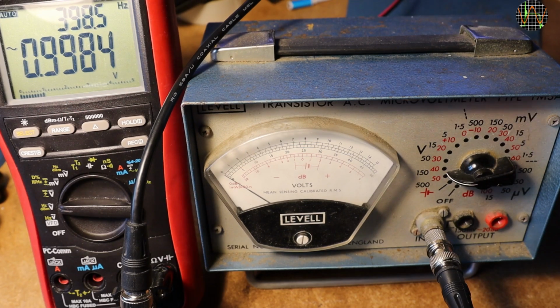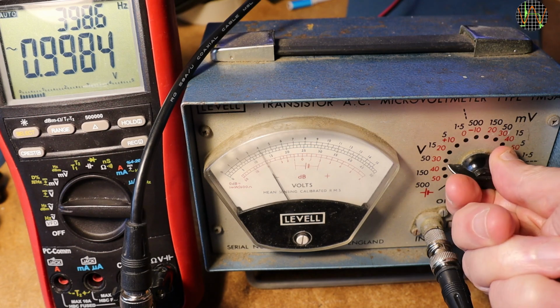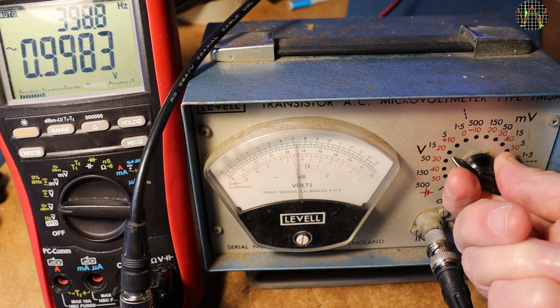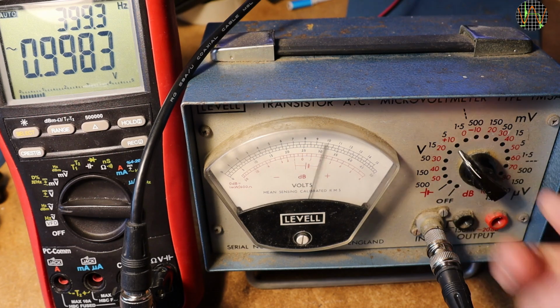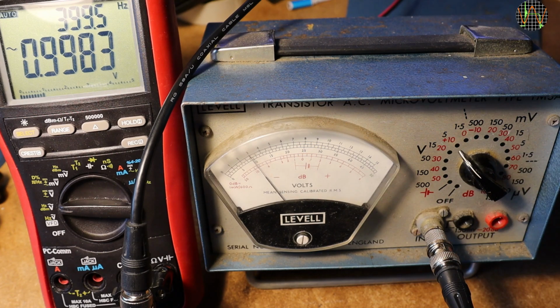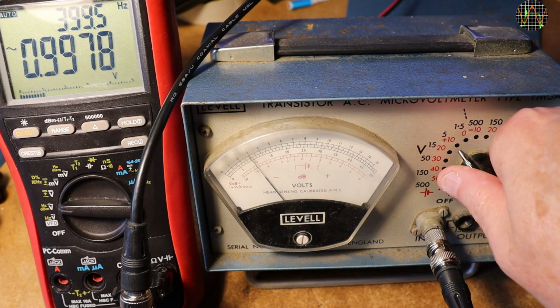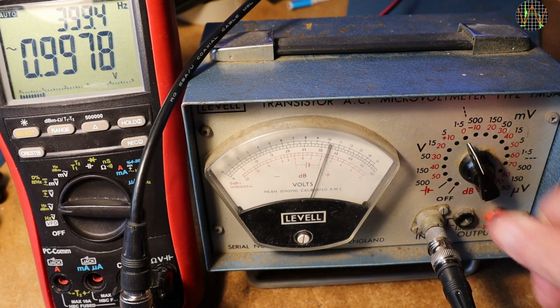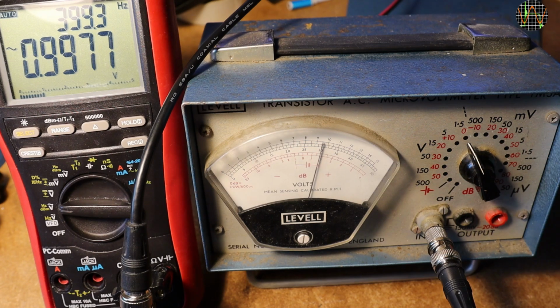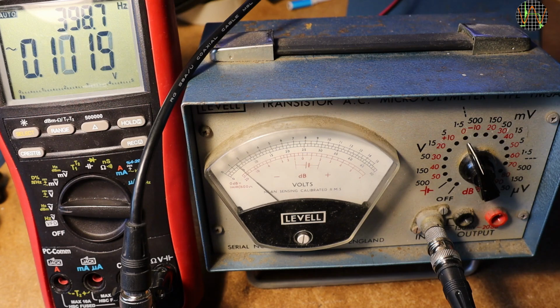I'm applying a sinusoidal AC voltage of 1 volt RMS at about 400 Hz, as you can see on the multimeter on the left. Apologies for the glare. The TM3A repeats the wild swings as I downrange to 5 volts. And after it comes down, the needle is roughly at the 10 on the lower black 0 to 50 scale. That is looking promising. Going to the 1.5 range, it right away moves to the 10 on the uppermost 0 to 15 scale, but then settles at a slightly lower value of 9.5, meaning of course 0.95 volts. Some calibration is probably needed.